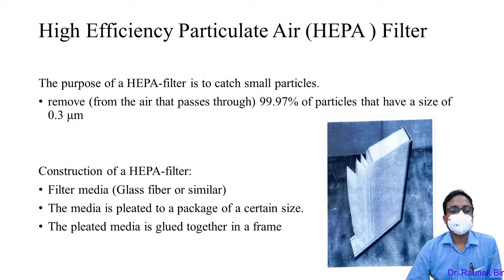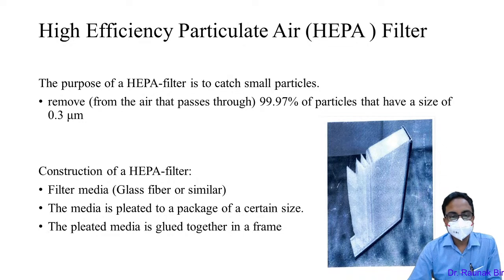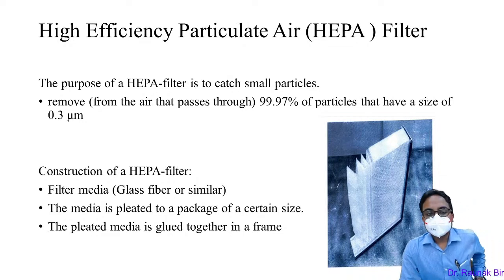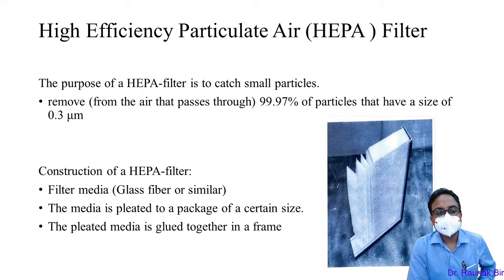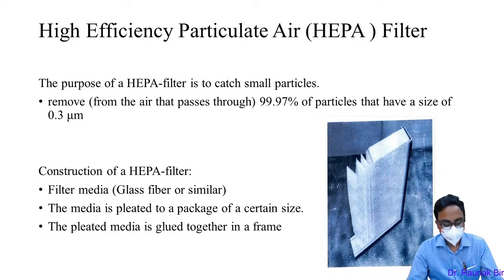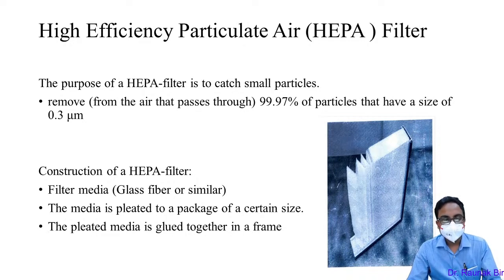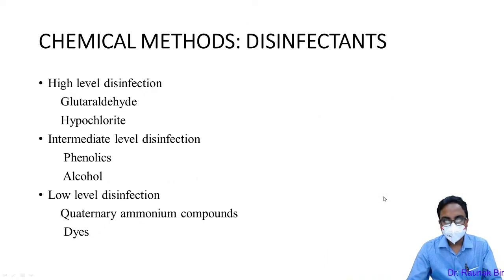Another type is the High Efficiency Particulate Air (HEPA) filter, which became well known during the COVID-19 pandemic. HEPA filters capture small particles and remove 99.97% of particles with a size of 0.3 microns from air that passes through. Construction involves glass fiber filter material pleated into various layers so the pore size decreases; the pleated material is glued together in a frame.